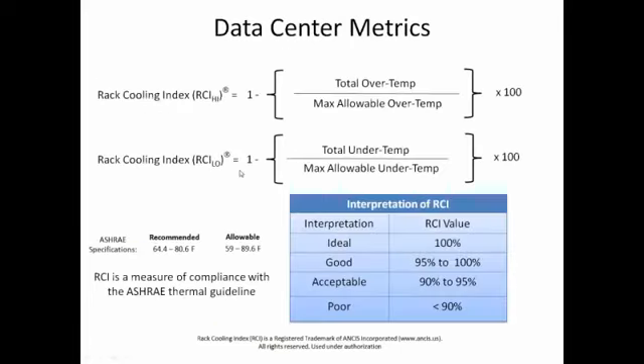The other one we're going to use here is RCI. And instead of going over this in a lot of mathematical detail, the rack cooling index deals with whether the rack inlets are conforming to the ASHRAE specification for temperature on the inlet. So you see here the recommended range for most cases, Class I. I realize these have been starting to be pushed up higher, but most people generally look at that recommended range as a first pass. They'd like to see their rack inlets between 64 and 80 degrees roughly of temperature.